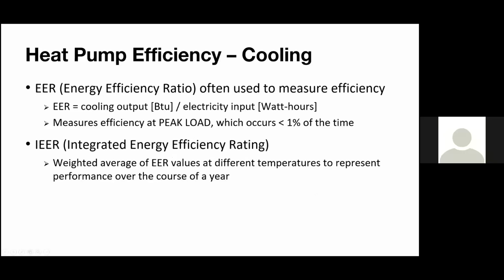So starting out, I'm sure a lot of you are familiar with this. This has been around for a long time, but EER, which is energy efficiency ratio. And this is the cooling output in BTUs divided by the electricity input in watt-hours, right? And the important thing to take away from here is this measures at peak load. The efficiency is measured at peak load, right? So peak load, again, would be that 95-degree day or that 0 to 5 degree day in the wintertime. So in the Boston area, if you are looking at bin data, how much time is actually spent at those temperatures, it's not that much.